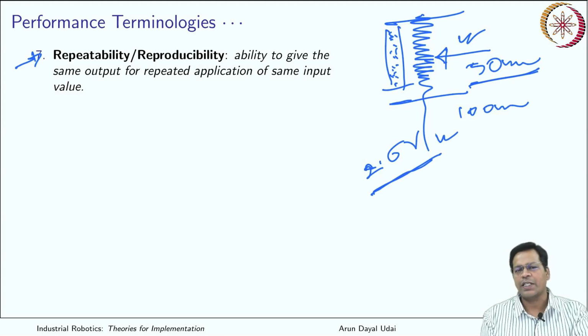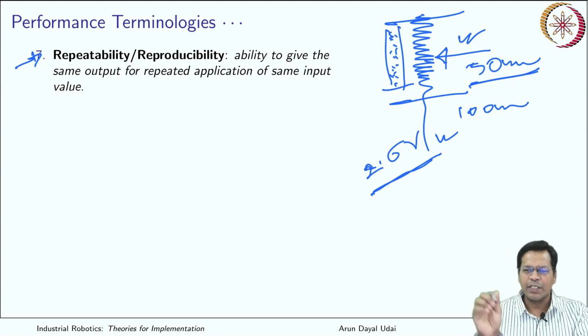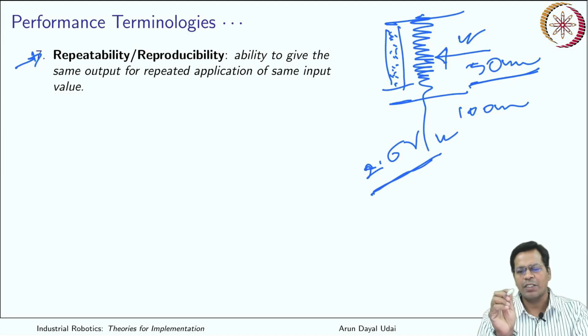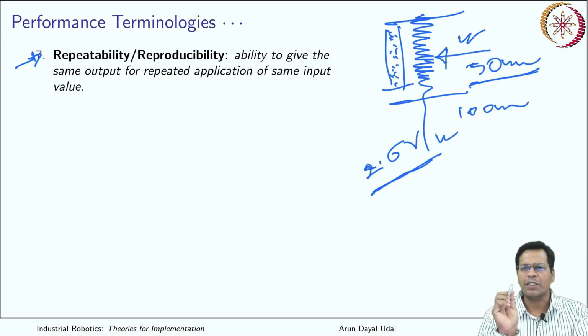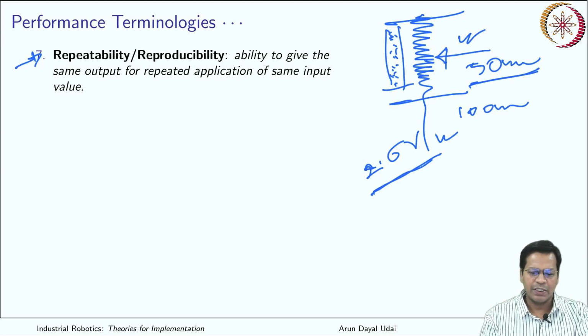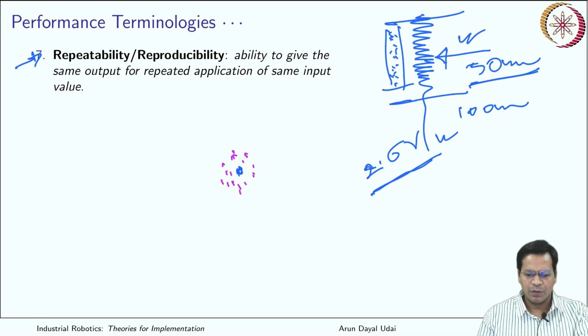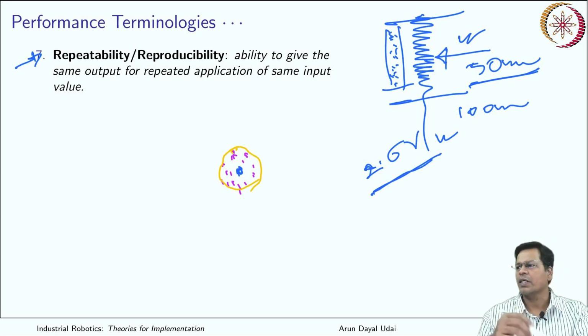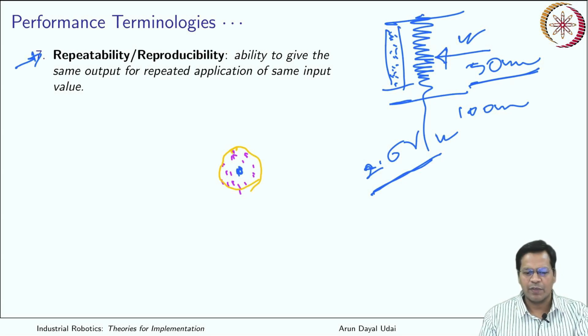In case of repeatability, at the same period of time—maybe on the same day—you measure multiple times and get different outputs. So basically, if this should be the output, you are getting signals somewhere over here. What is repeatability? It is defined as the smallest circle which should contain all the data for a given value.